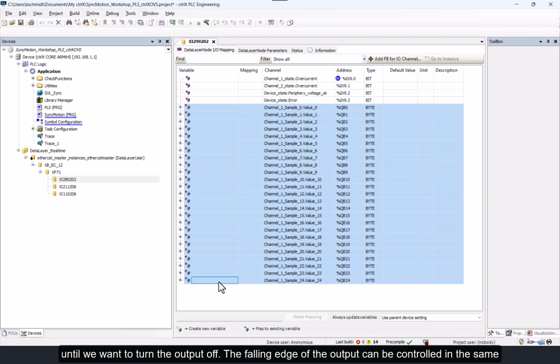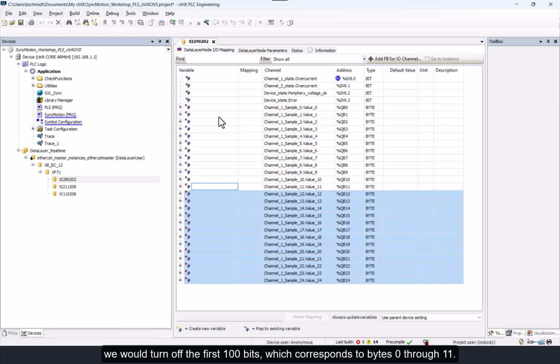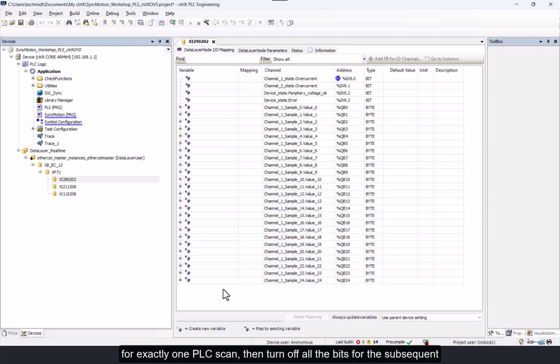The falling edge of the output can be controlled in the same way. If we need the falling edge to occur exactly halfway through the EtherCAT cycle, we would turn off the first 100 bits, which corresponds to bytes 0 through 11, for exactly one PLC scan, then turn off all the bits for the subsequent PLC scans. If we had activated two channels with 200 times oversampling, then we would have bytes 25 through 49 corresponding to the second channel. This is just for your understanding. The digital cam switch function block will control these bits automatically based on on and off positions and other settings.